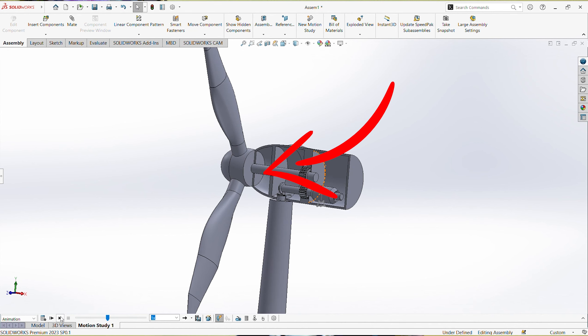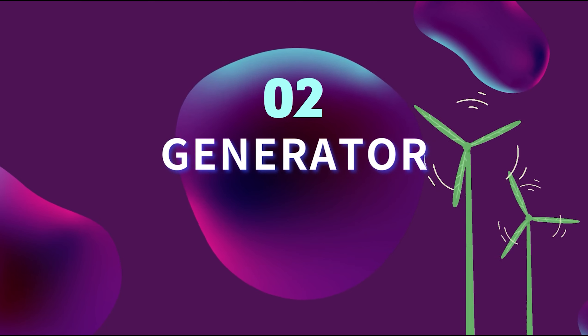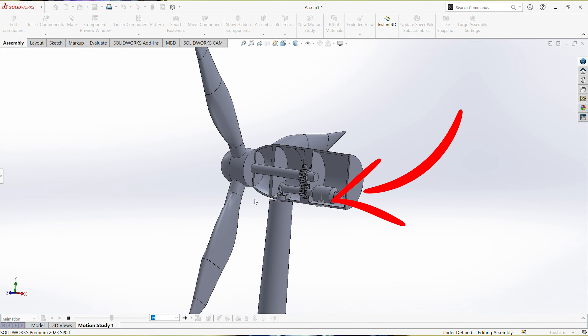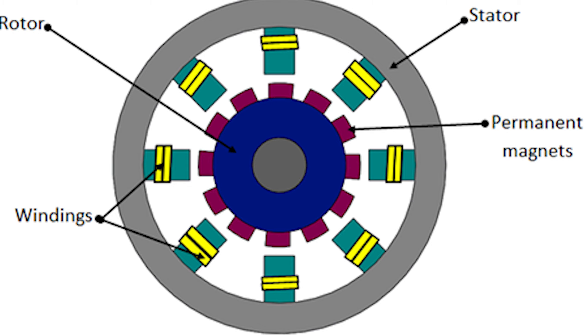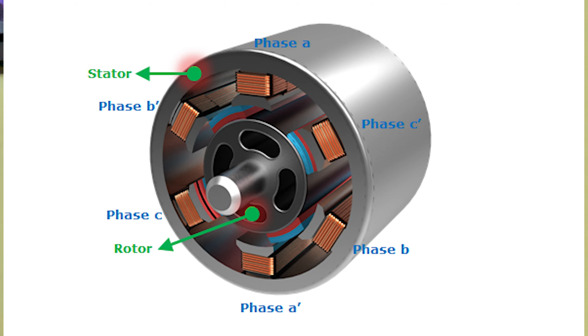The first principle is rotational motion — the most important one, because all the mathematics, blade design, and aerodynamic analysis helps improve the performance of the rotational motion. It is because of this rotational motion that mechanical energy is produced. The blades are connected to the shaft, and this shaft transfers the mechanical energy to the generator to create electrical energy. The generator is typically located inside the nacelle, which is the housing at the top of the wind turbine tower. The generator has two components: the rotor and the stator. The rotor is attached to the shaft, and mechanical energy is transferred from the shaft to the rotor, causing the magnets on the rotor to cut the magnetic field lines of the poles to create electrical energy.